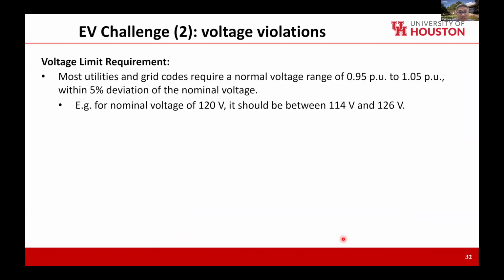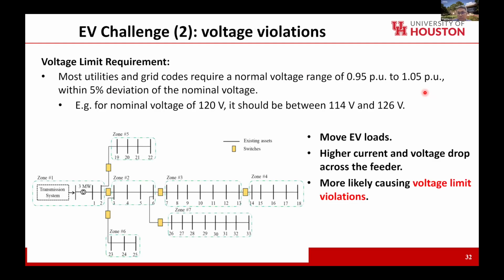A second challenge is voltage violation. For the power system, we need to maintain a nominal voltage range between 0.95 per unit and 1.05 per unit. Per unit here means normalized voltage magnitude, so it's a 5% deviation from the nominal voltage that we can tolerate. If it's more than that, there will be power quality issues. If we have more loads, the cables need to carry greater current, so the voltage drop will increase across each feeder segment. If the voltage drops too much, then at the end of the feeder lines we may see undervoltage issues.